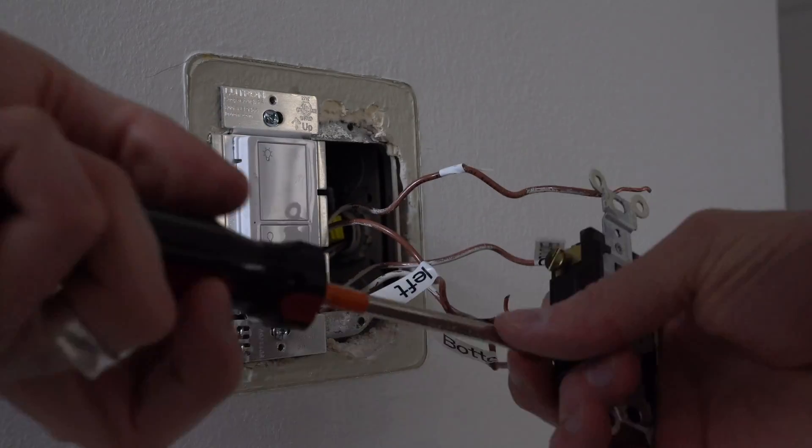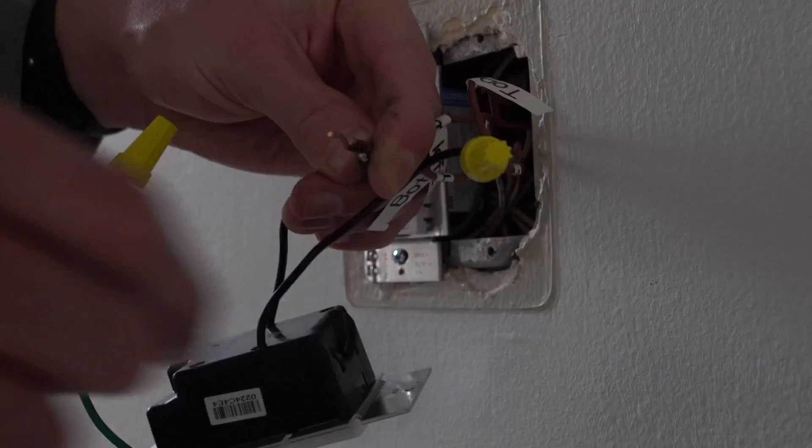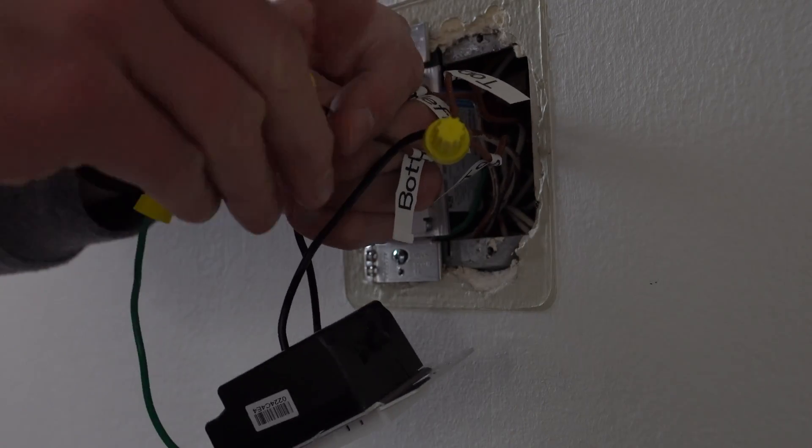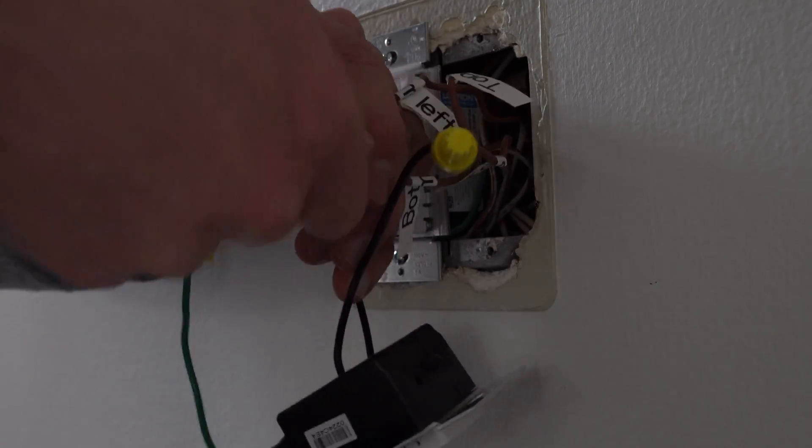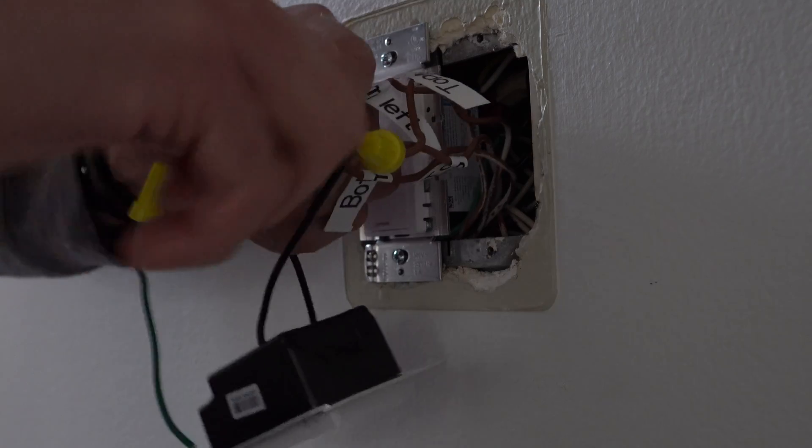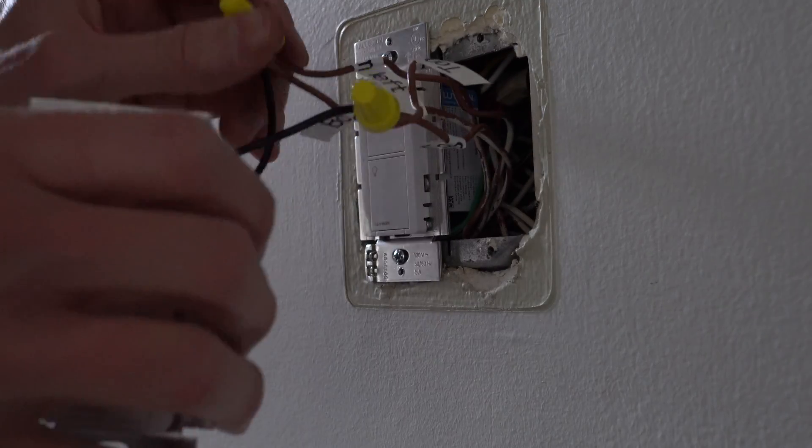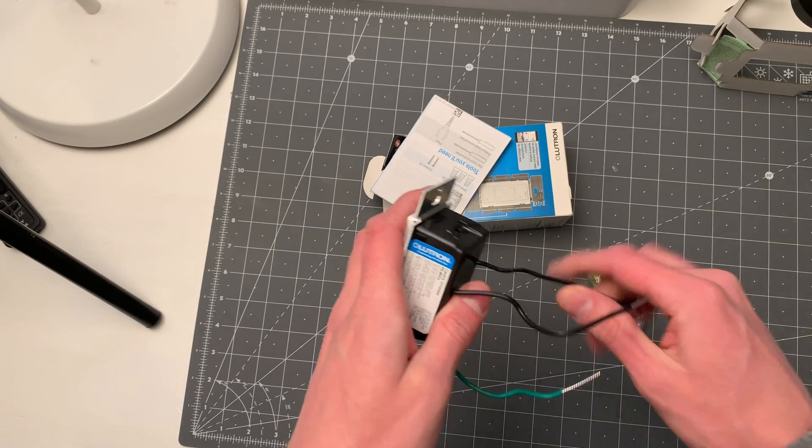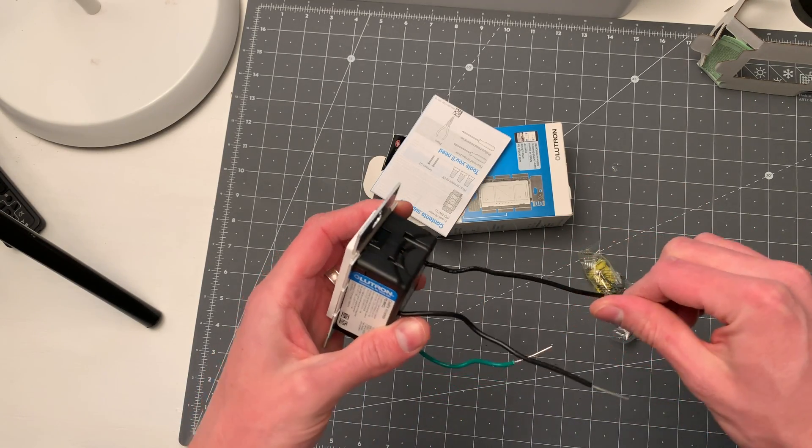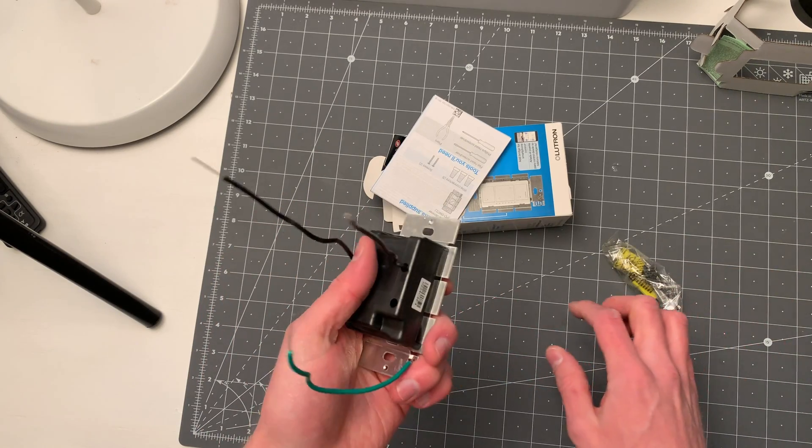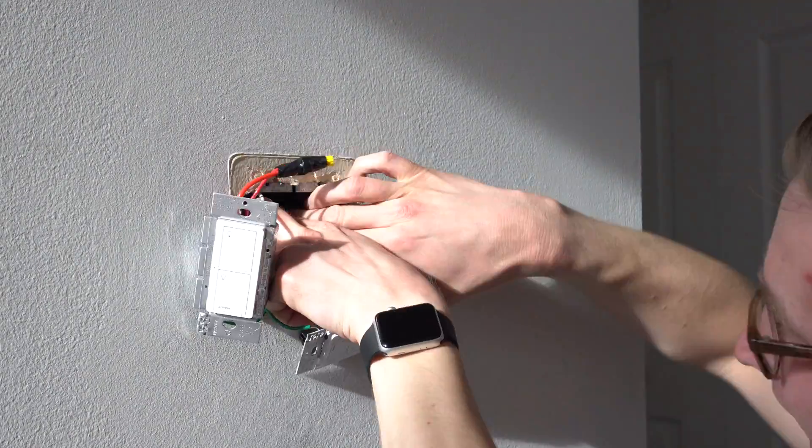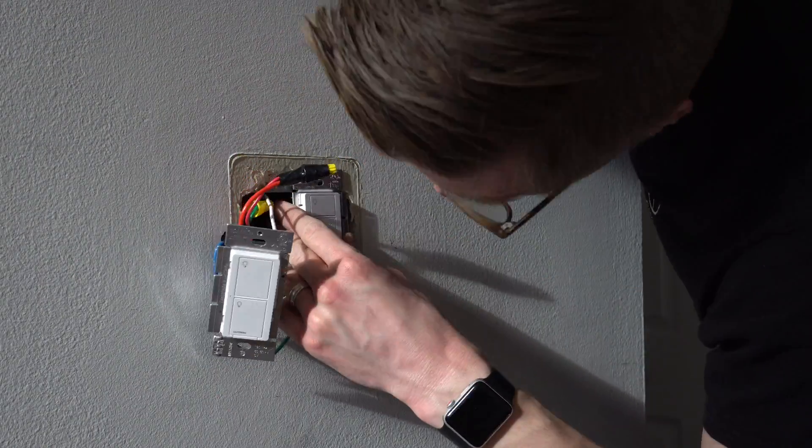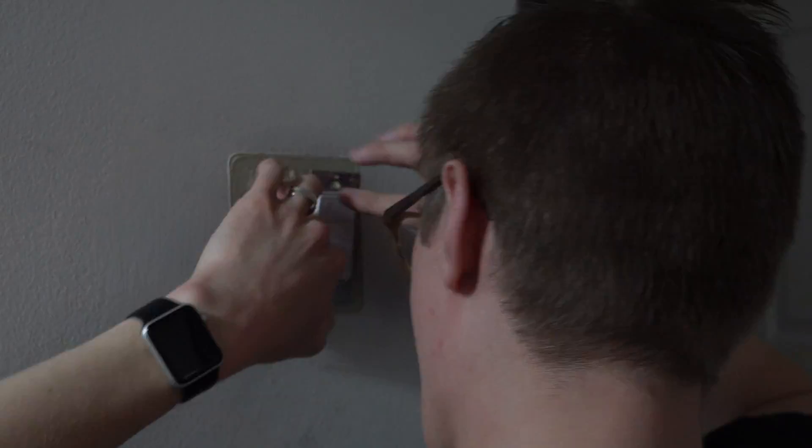But from there today, once you've labeled those, we want to take the two top wires and merge those together. And then the two bottom wires and merge those together. And then you connect each one of those sections with one of the black wires from the dimmer switch. So then one part of the dimmer switch circuit is controlling the top two wires and the bottom part of it, another part is controlling the bottom two wires on the dimmer switch. So from there, just cap everything off, tape it up and put it back in the switch box.